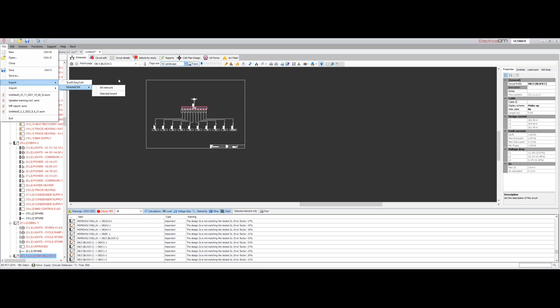I can even break it down into smaller parts. So if you've got multiple engineers out on site, I can send this part to one engineer, this set of boards to another. They can complete the testing on the mobile app and check the data's right compared to what's there. They can send that back in, and when we import, the software will immediately pick out where things like protective devices or cable sizes have been changed, and bring all the test data back in immediately, putting it into our test data.